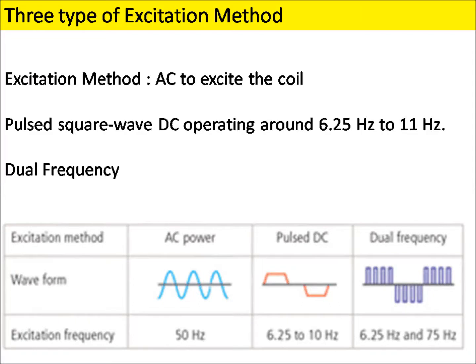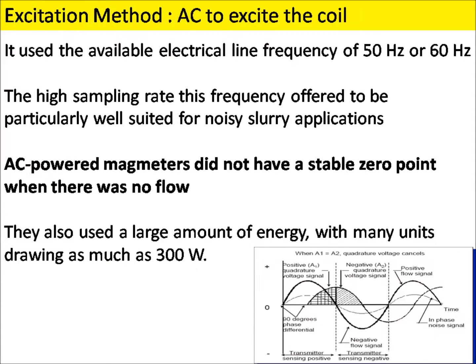Three types of excitation method are used in a magmeter to excite the magnetic coil. They are AC excitation method, DC excitation method, and dual frequency excitation method. Since their introduction in the 1950s, magmeters have evolved enormously from a technology standpoint. A typical meter from the first decade would have used AC to excite the coil, so it used the available electrical line frequency of 50 Hz or 60 Hz. Users soon found the high sampling rate this frequency offered to be particularly well suited for noisy slurry applications, and it offered fast response to changes in flow rate.